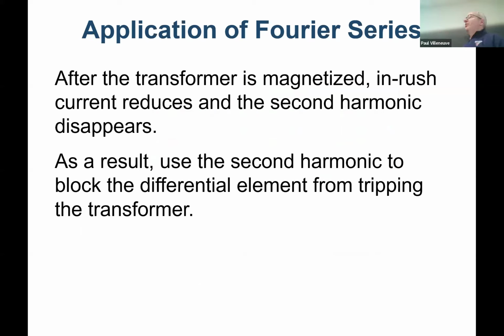And interestingly enough, there were 2 relays. There was one GE and one SEL relay that were set up. And they actually had 2nd harmonic blocking enabled. The problem is the GE needed 2 out of the 3 phases to show high 2nd harmonic to block it. The Schweitzer only needed to have 1. So any 2nd harmonic component would block.